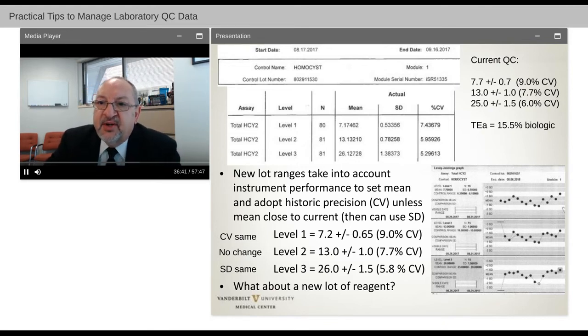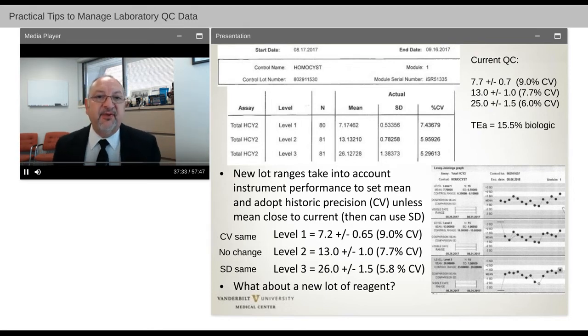So historically, over time, we've been running, and here you can see current QC up in the upper right-hand corner. We are running at 9% at 7.7, and the high QC is 6%. Total allowable error for this biological is 15.5%. We run this QC over 20 days on four different analyzers, so we get 80 points here. And these are our means in the upper left box here, 7.17, 13.13, 26.12. So the new lot ranges have to take into account that the QC may be slightly different in terms of mean.